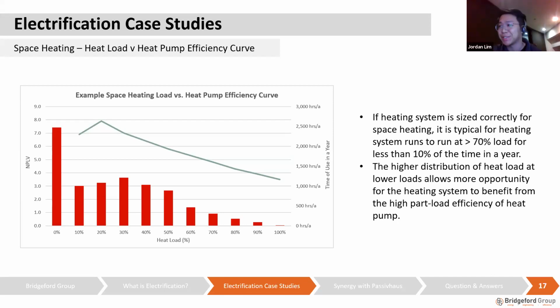Well, I wish my fellow design engineer were here. I am an energy engineer by trade, but to size up the system, well, we at Bridgeford Group come from a retrofit background. I wonder if you're asking from a retrofit point of view or from a new building point of view, but the way you size up your hydronic heaters and your space heaters wouldn't be too much of a difference, honestly. Historically, you would have to account for the different types of heat losses from in-floor electric hydronic heaters and also for space heaters. But with heat pumps, the thermal capacity suggested, with any new development these days, you would have to do your Section J assessment. You would have to do your energy modeling anyway, and so the energy metrics that you get as a result from the Section J assessment and also from the thermal energy software would be your best source of information to help you size up your system.